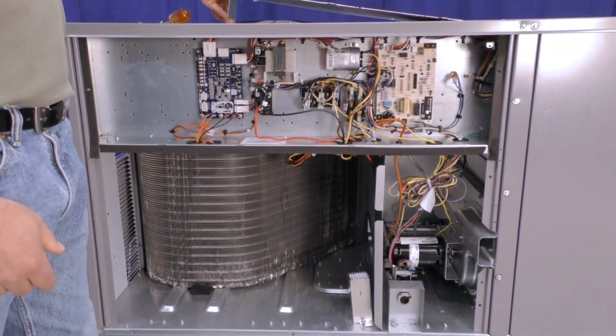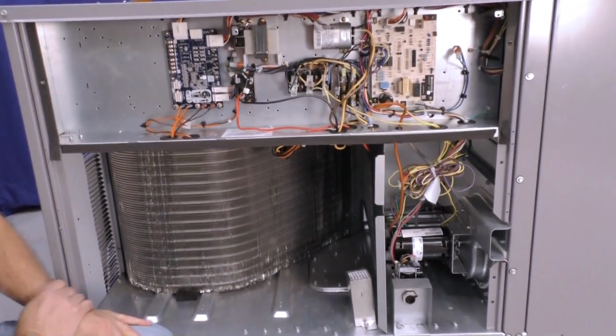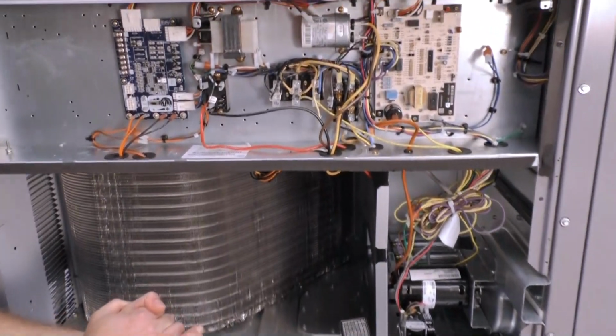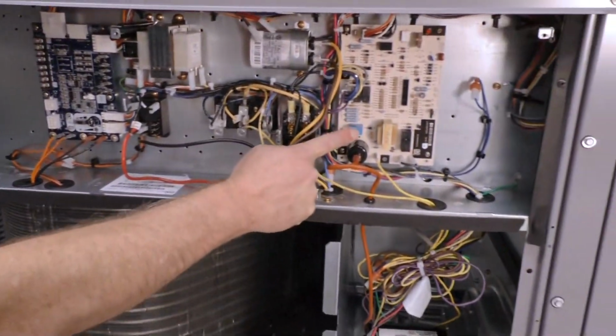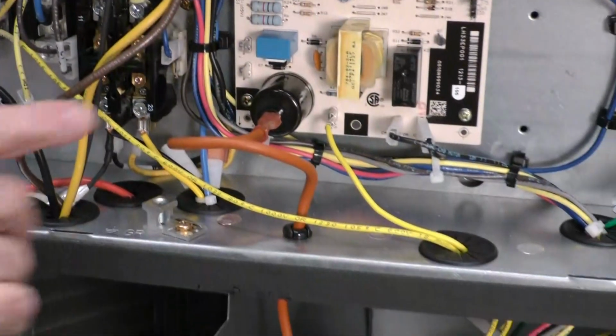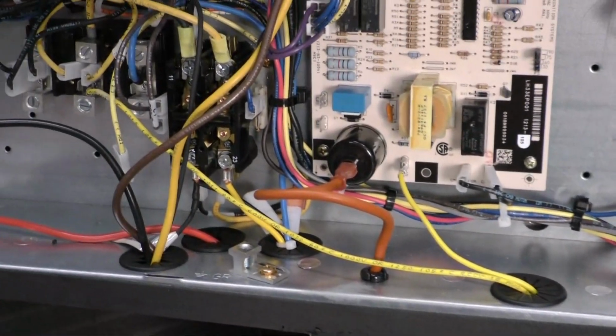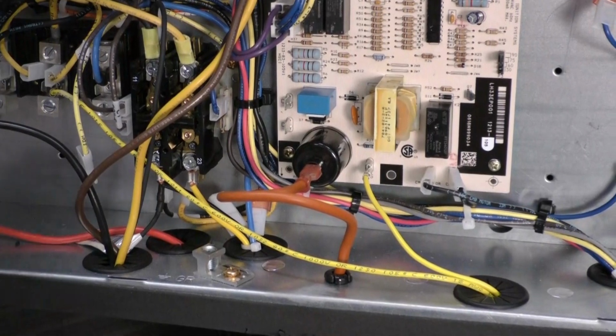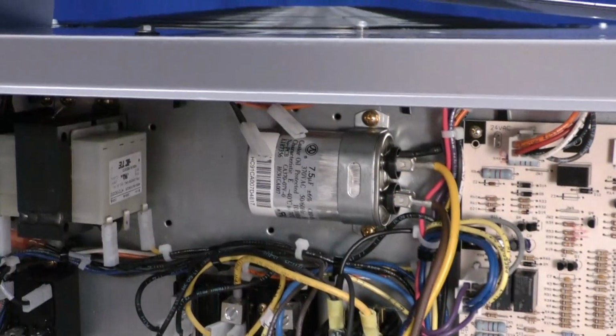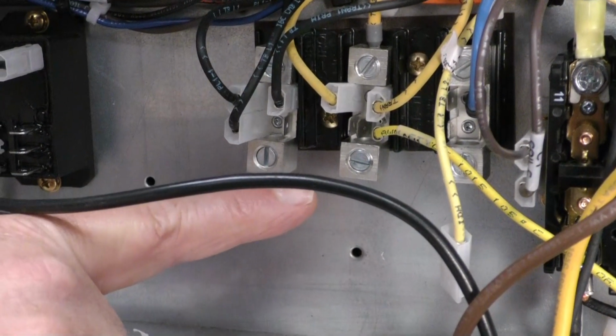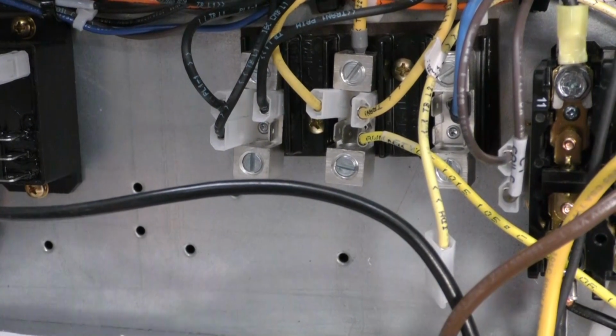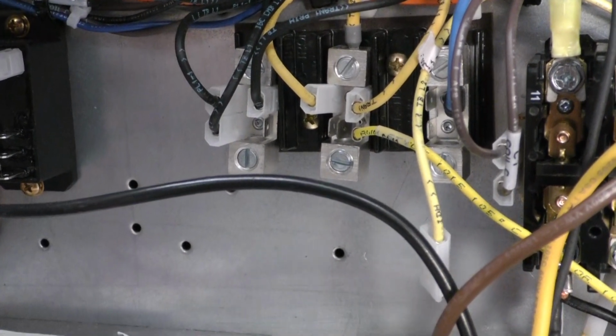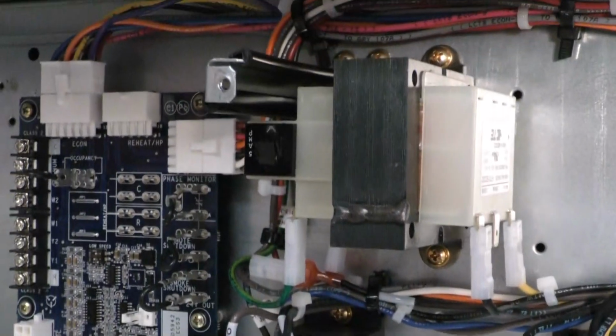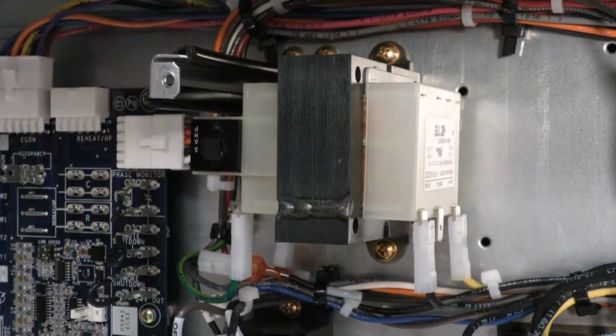Removing that panel exposes the balance of the control box components. As we can see, this is a gas heat machine, so it has an integrated gas control module. This is the newer integrated gas control module that uses a pressure switch for combustion fan proving. We've got a run capacitor for our outdoor fans, a contactor for our compressor. This is a three-phase unit, so we've got a 3-lug terminal connection for our incoming high voltage power. Our control voltage transformer, and our new fan control board.